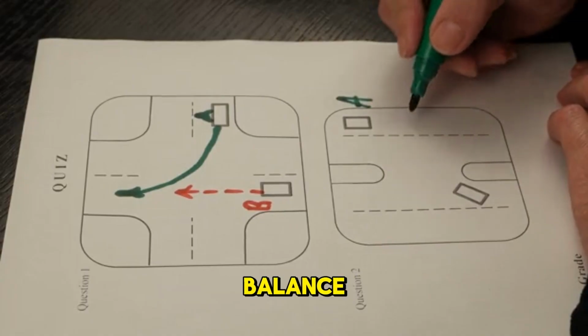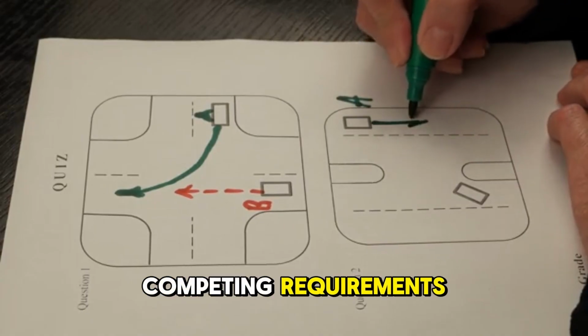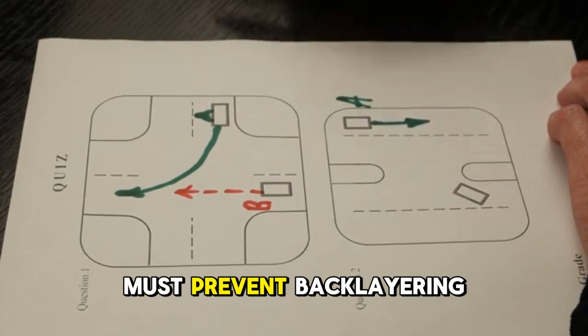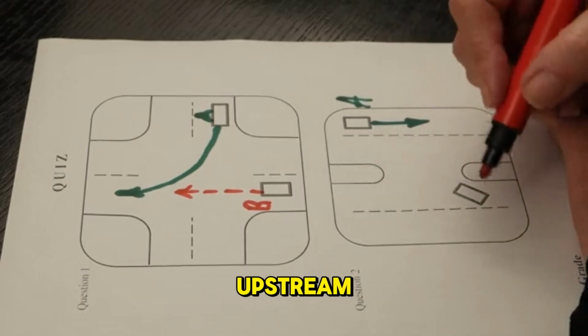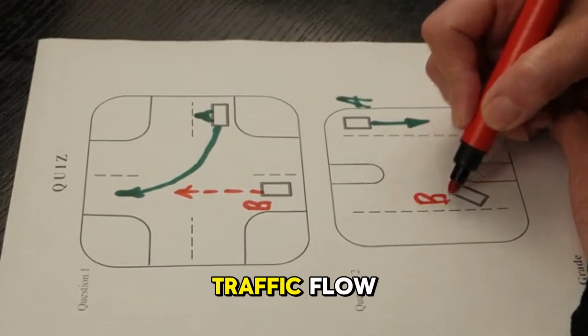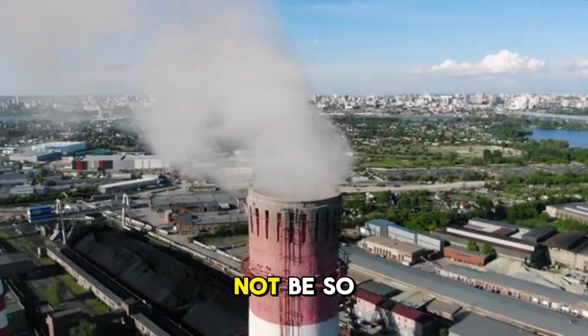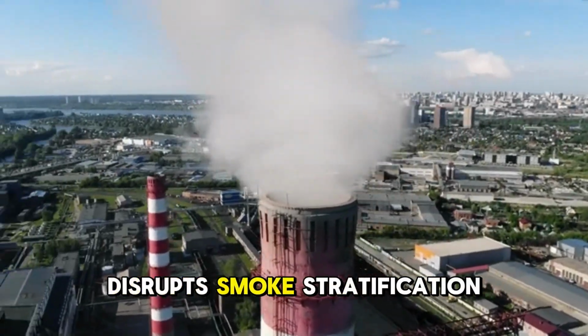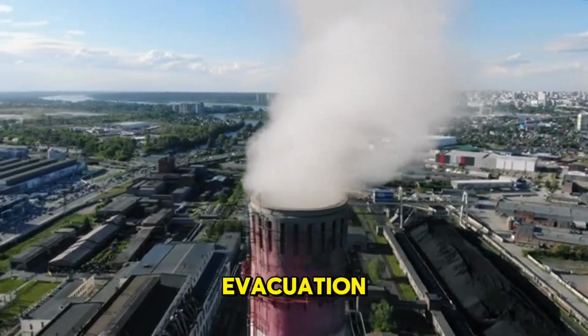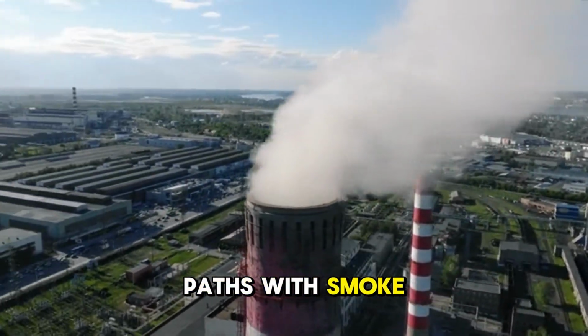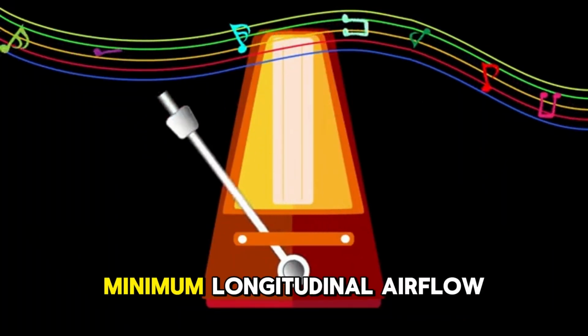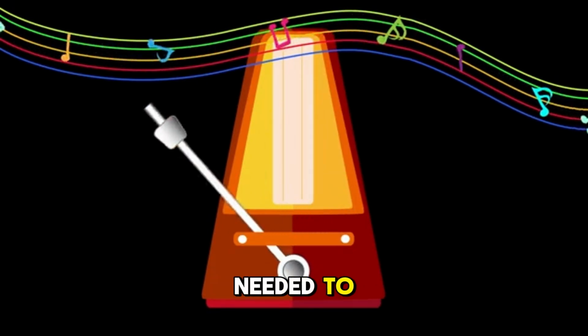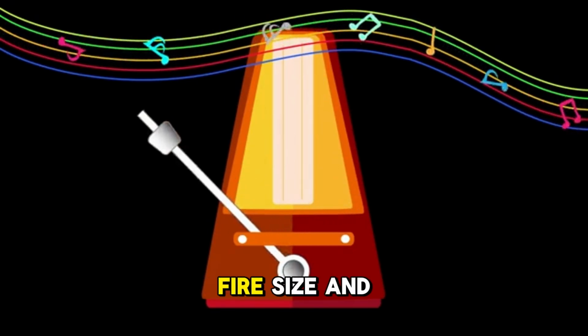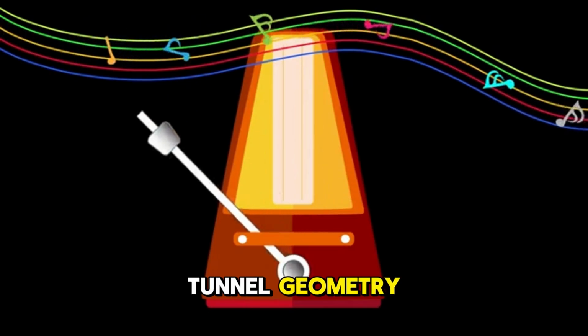Emergency design must balance competing requirements. Longitudinal airflow must prevent backlayering, which is the upstream spread of smoke against traffic flow. But airflow must not be so high that it disrupts smoke stratification and fills the evacuation paths with smoke. The critical velocity is the minimum longitudinal airflow needed to prevent backlayering for a given fire size and tunnel geometry.